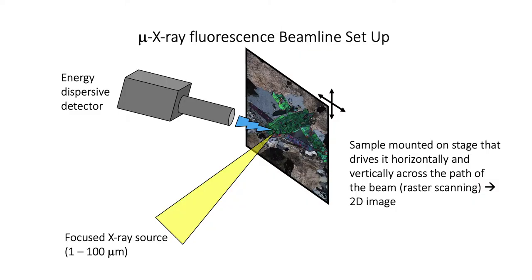At a micro x-ray fluorescence beamline, the sample is mounted on a stage that drives horizontally and vertically across the path of a focused x-ray beam. This method of measurement is called raster scanning, where the beam stays fixed in place and the sample is scanned across it in order to generate a two-dimensional image. When the focused x-ray beam hits the sample, it causes the elements in that sample to fluoresce, which is then measured by the energy dispersive detector.